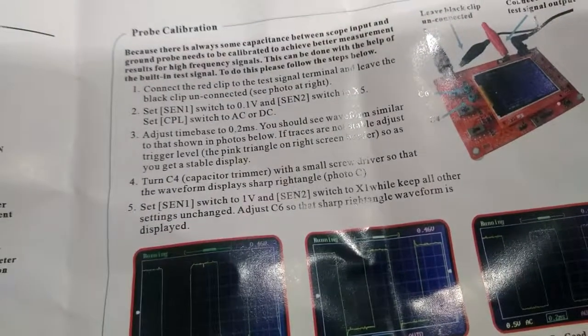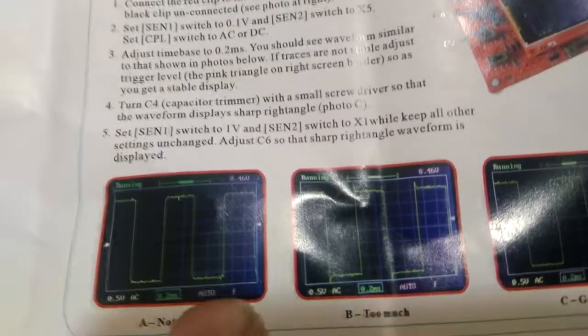Alright, as far as the calibration goes on this test signal, you've got this little explanation here. It basically says put it on 0.1 volts sensitivity x5, and at 0.2 milliseconds, that's what your waveform is going to look like roughly. And what you're trying to do is trim down that little whisker coming off the bottom end of your square so that it's flat, generally looking like that right there. Now that doesn't look perfect, but it's close enough, whereas that's got a little bit of a roll off.